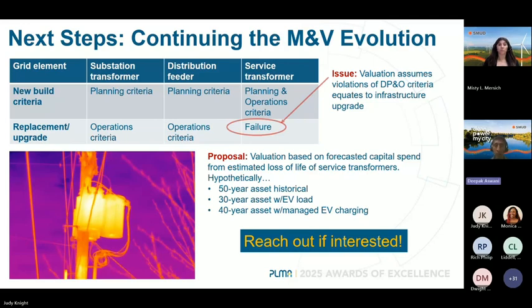So our proposal is to think about valuing benefits for service transformers differently. Rather than focusing on the overload criteria, we focus on how we're impacting the loss of life for the transformer, looking at the real world depreciation of that transformer. That may not be accurate on an individual transformer basis, but for a fleet of 50,000 or 100,000 transformers, it might have statistical significance.